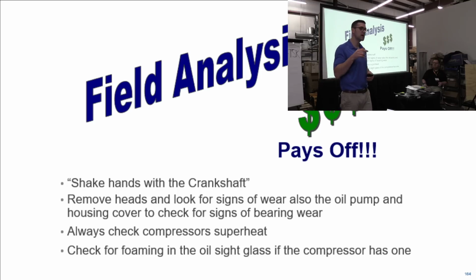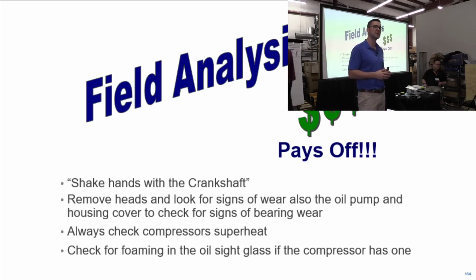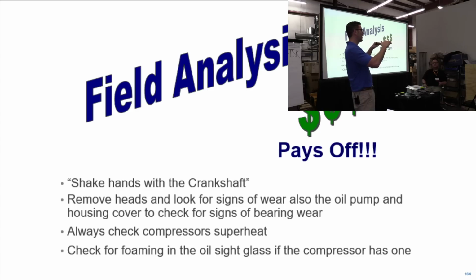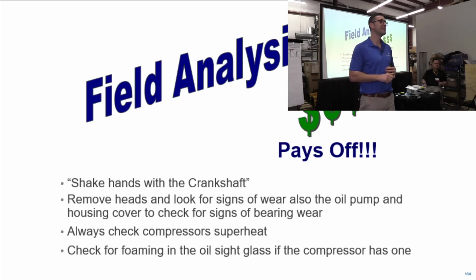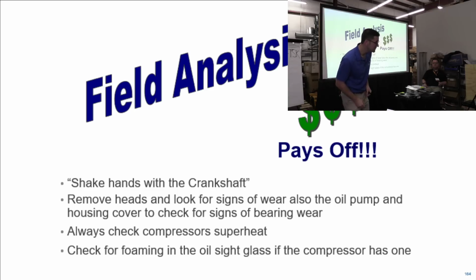One thing, if you walk up to a compressor and you look in the sight glass and it's full of foam or full of bubbles, what does that mean? Say a scroll, you go up to a scroll and you're looking inside and there's a nice half sight glass of oil, and all of a sudden you start seeing foam and foam and foam. What does that mean? Contamination. That's liquid flooding back. So that's one sign. You could just walk up to a compressor and look inside. Ooh, that doesn't look good. Figure out why that's happening.